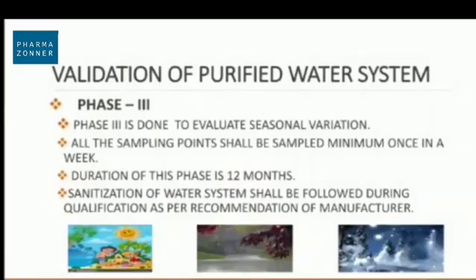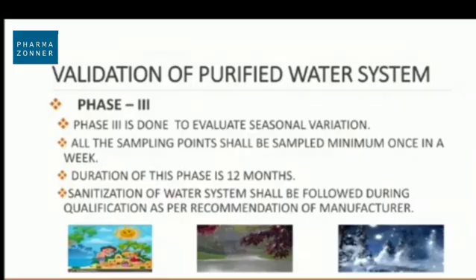Phase Three is done to evaluate seasonal variation. When seasons change, source water quality changes, and the impact on final water quality is evaluated. The duration of Phase Three is 12 months. All sampling points shall be covered minimum once per week, and critical points such as generation point, storage point, and return loop point can be analyzed on a daily basis. After 12 months, trends are compiled and a final report is prepared.